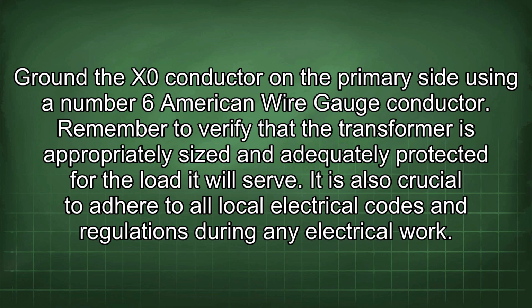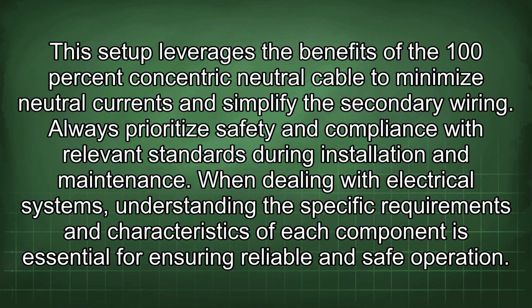Remember to verify that the transformer is appropriately sized and adequately protected for the load it will serve. It is also crucial to adhere to all local electrical codes and regulations during any electrical work. This setup leverages the benefits of the 100% concentric neutral cable to minimize neutral currents and simplify the secondary wiring. Always prioritize safety and compliance with relevant standards during installation and maintenance.